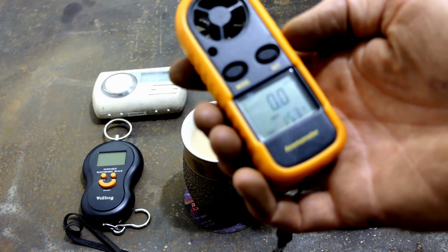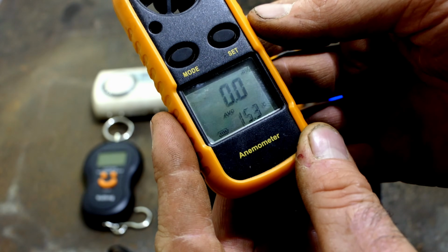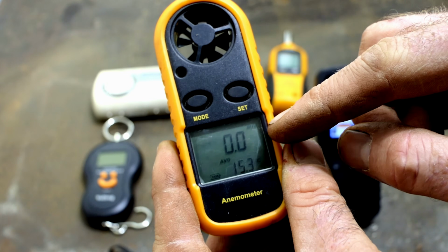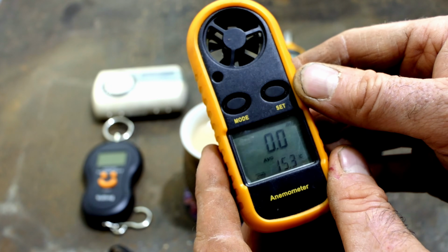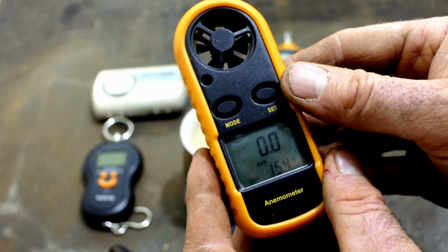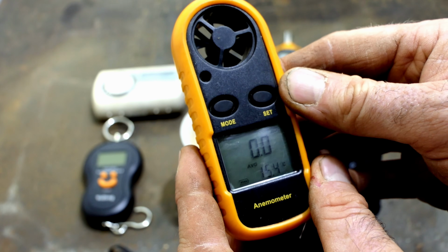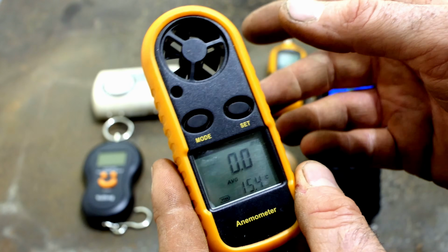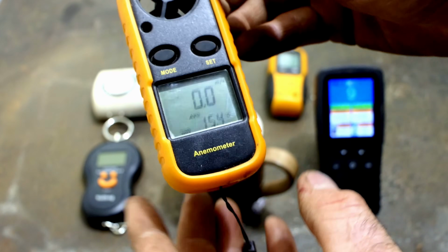Next, I've got the anemometer, which gives us both a flow rate and temperature reading. With this, we should be able to work out exactly how much energy is being lost through the exhaust, and how much is coming out of the blower into the room. That way we can figure out how well our heat recovery system is working.